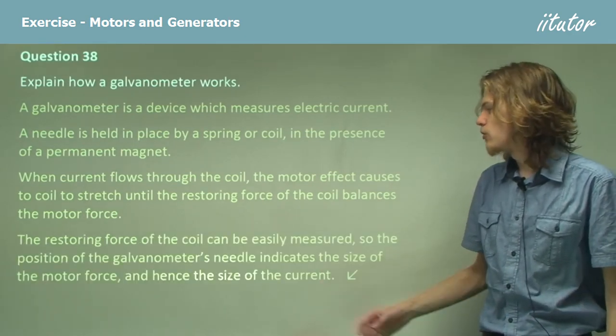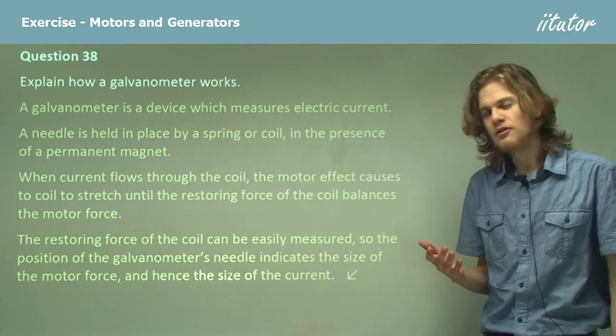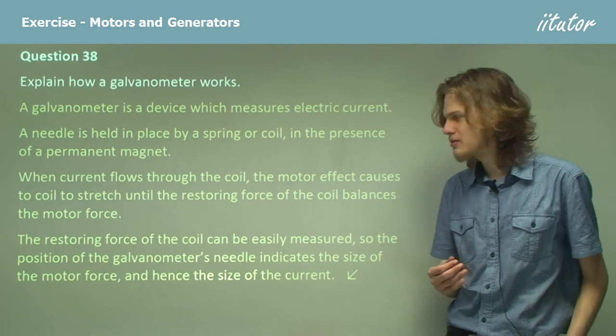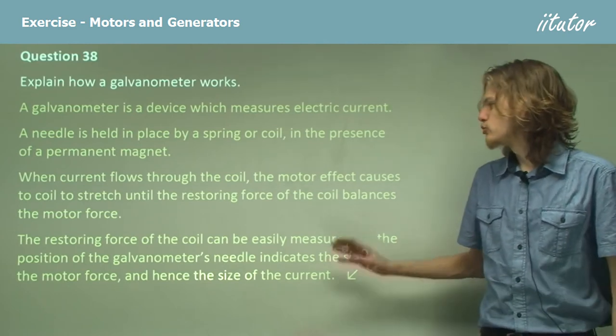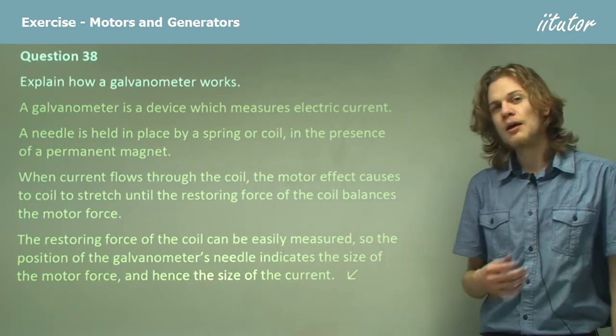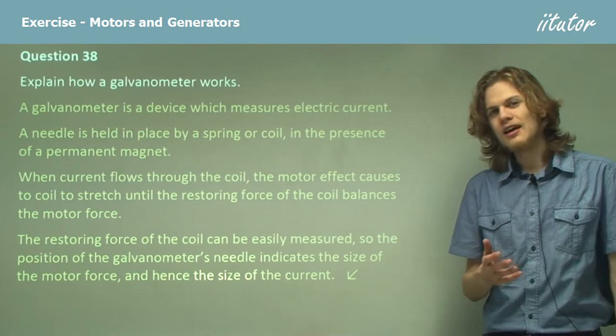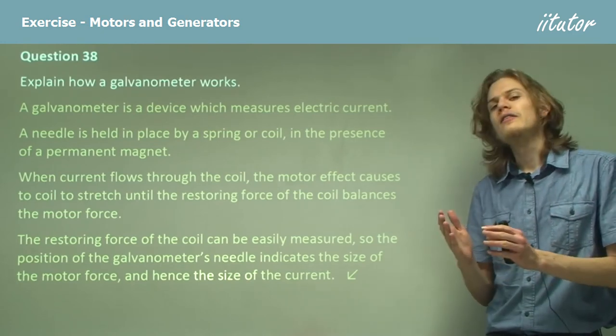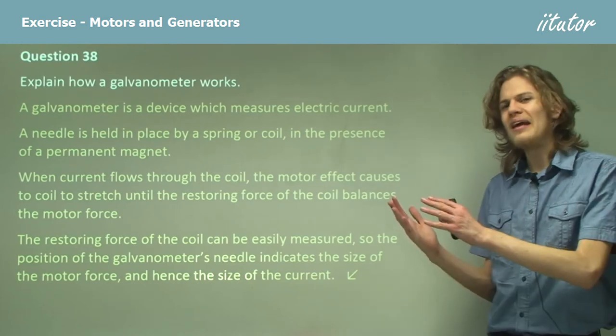The restoring force of the coil can be easily measured. There is in fact a fairly handy equation that will tell you exactly how much restoring force a spring has. So the position of the galvanometer's needle can be calibrated. We can say that if it's exactly this amount of force, then that'll equate to, you know, one ampere or something.